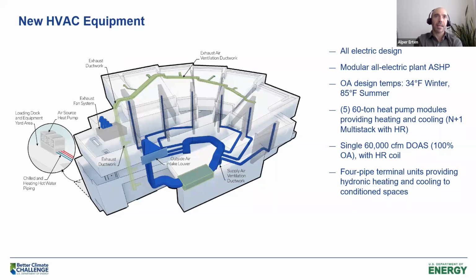To serve all the loads in the lab program and other spaces, the design team has chosen to go with a hydronic cooling system approach. In this approach, we had a dedicated outdoor air system on the roof, coming from the outside air intake louver you can see on the image, keeping the same 60,000 CFM capacity. The remaining cooling and heating is provided with 4 pipe terminal units at each space. These terminal units get heating hot water and chilled water from the building central plant. They have individual heating coils and cooling coils at each zone.